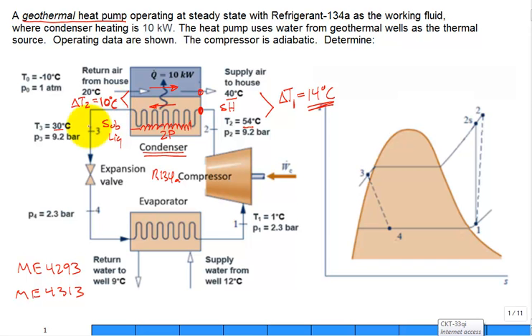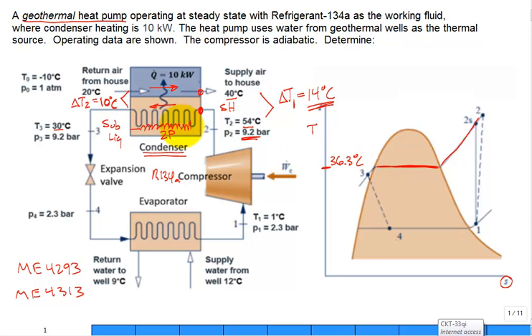So from the outside this should work. But as we know, right on this temperature-entropy diagram, as you change phase you're going to come down and then spend a lot of time at a constant saturation temperature for the condenser pressure. At 9.2 bar, that's about 36.3 degrees C. So a lot of the refrigerant within this heat exchanger is around 36.3 degrees C. It comes in at 54, desuperheats to saturated vapor, then condenses, and comes out at 30 degrees C — sub-cooled a little bit.